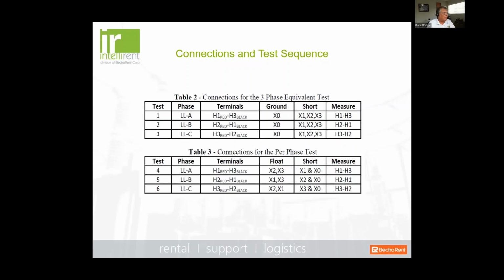Now, basically we're going to do two types of tests: the three-phase equivalent test and the per phase test. And you'll notice that we're doing a three-phase equivalent. Okay, we have shorted out, because it's a short circuit impedance test. We're going to measure the impedance between H1, H3, H2, H1, and H3 and H2. Okay, so this will give us an equivalent three-phase impedance circuit measurement. And then we're going to do it per phase, okay, H1 to H3, H2 to H1, and then short the X bushings accordingly according to our connection diagram.